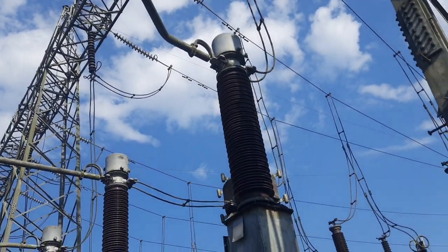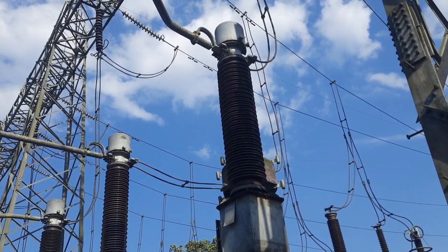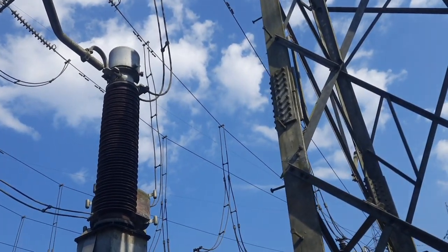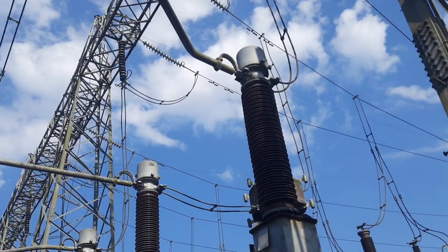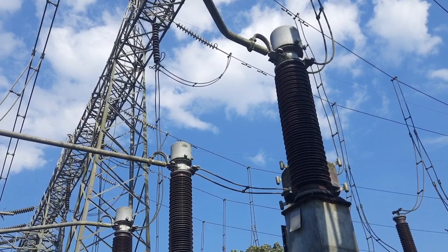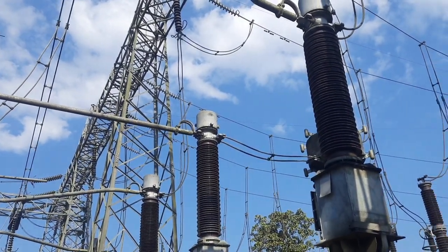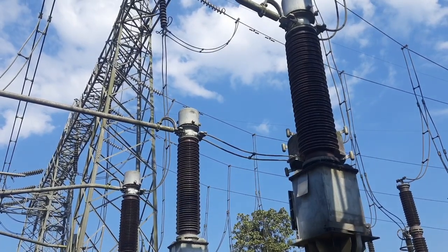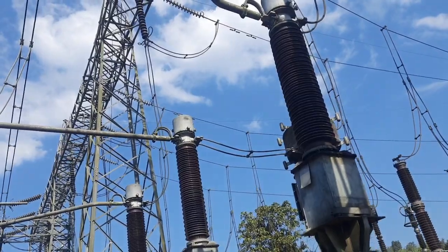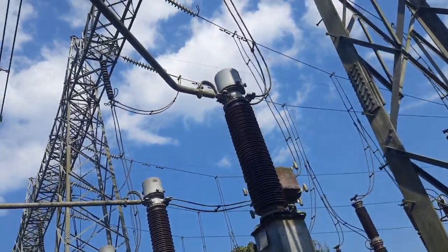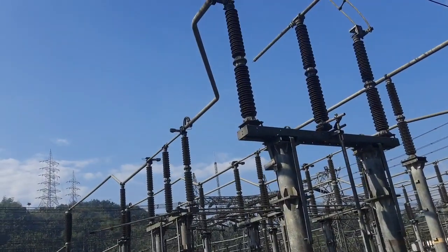So after the CVT and Wavetrap comes the CT, which is your fourth element. First come the surge arresters, then the CVT, then the Wavetrap, and then the CT, which is actually the third element in the case of the R and B phases, because we are not using the Wavetrap there. It is not needed to trap the high frequency there. After the CT, the arrangement has the isolators and your breaker also. This is as per the requirement. Where do we want to place it?